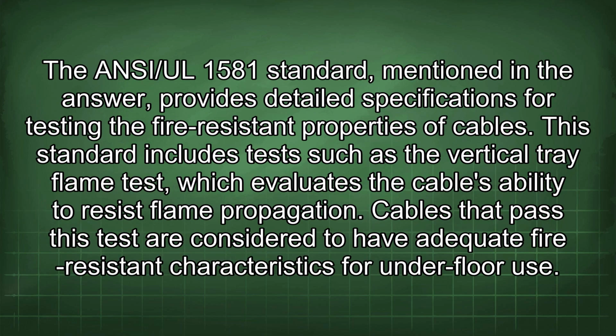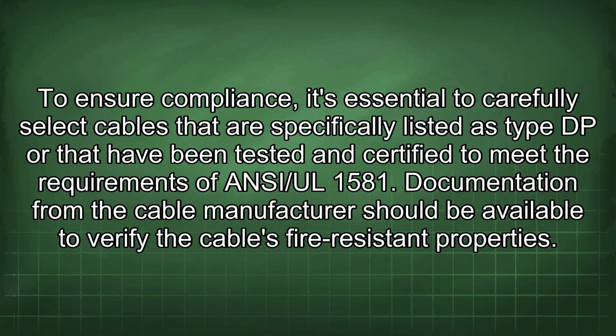The ANSI/UL 1581 standard, mentioned in the answer, provides detailed specifications for testing the fire-resistant properties of cables. This standard includes tests such as the vertical tray flame test, which evaluates the cable's ability to resist flame propagation. Cables that pass this test are considered to have adequate fire-resistant characteristics for underfloor use. To ensure compliance, it's essential to carefully select cables that are specifically listed as Type DP or that have been tested and certified to meet the requirements of ANSI/UL 1581. Documentation from the cable manufacturer should be available to verify the cable's fire-resistant properties.